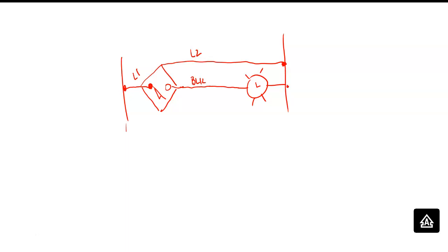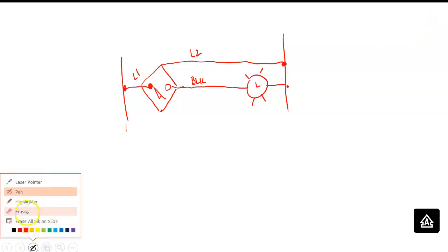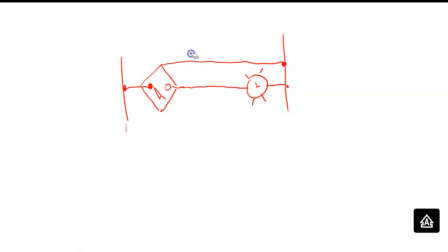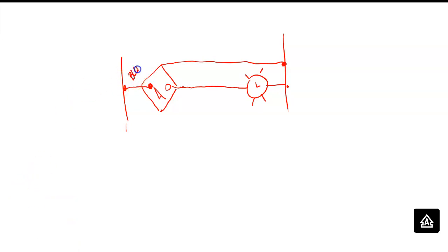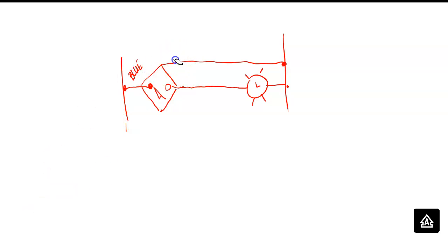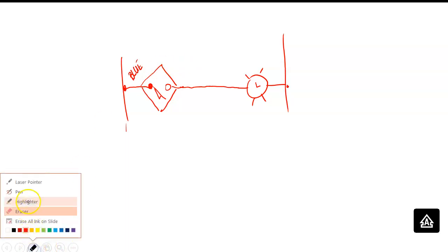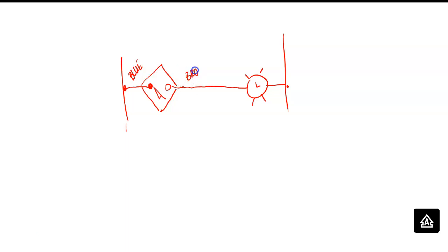So the sensor that we'll use is a 2-wire sensor. It only has 2 wires, and it's AC. So it doesn't really make any difference which way you hook it up, but it does, because you want to maintain the code between your 2-wire sensors and your 3-wire sensors. So this over here is going to be blue, I hope it is. And this right here would be brown. So you need to make sure the blue goes toward L1 and the brown goes toward L2.